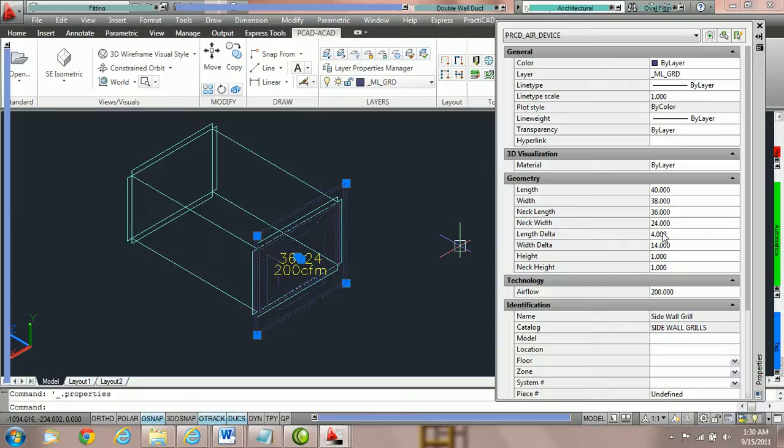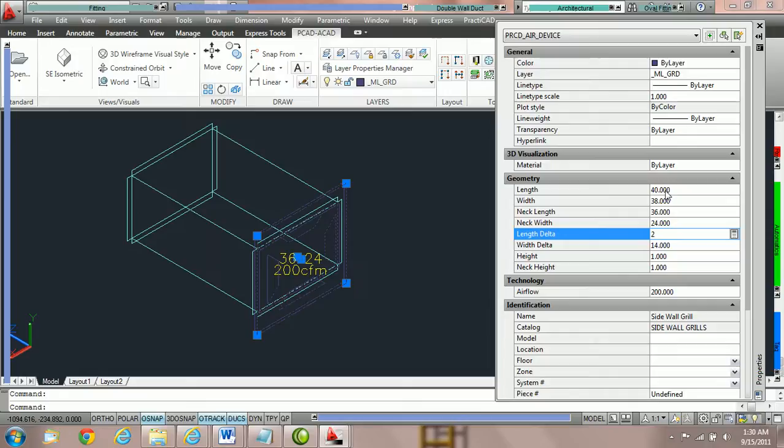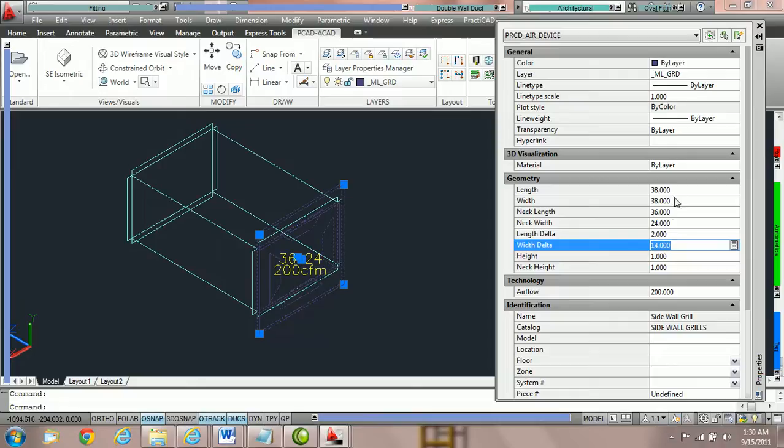So if we wanted to have a one inch flange all the way around the face of the grill, we'd actually want two inches of delta. So we'd put in for length delta, we'd put in two. And once we hit enter, PractiCAD is going to take two, add it to the neck length and adjust the length. So the length should adjust to 38 once we've done this. So currently we hit two and adjusted it to 38.